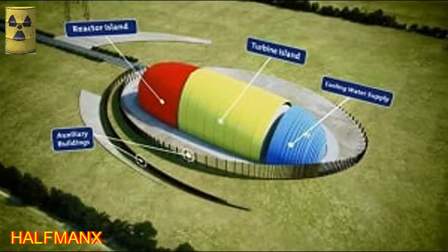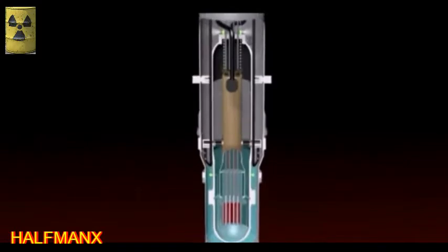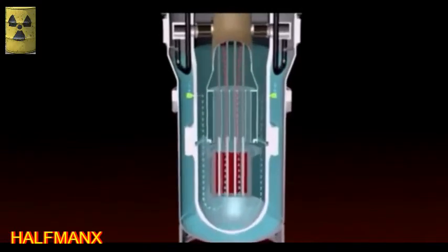As well as the potential design changes and increased security, it faces important security questions, which include potential problems with the system that automatically shuts down its reactors in an eventual emergency. NuScale's SMR employs natural water circulation to passively cool its reactor down. Normally, convection circulates water laced with boron to control the nuclear reaction to the core of NuScale's reactor. If the reactor overheats, it shuts down and the valves release steam into the containment vessel where it condenses and flows back into the core.